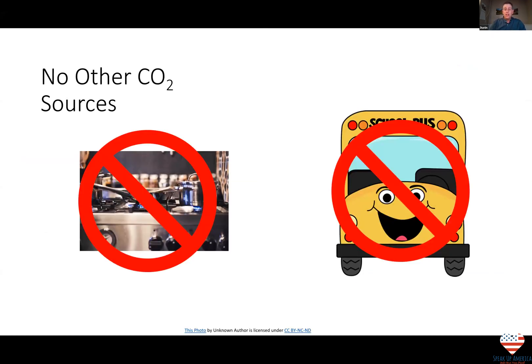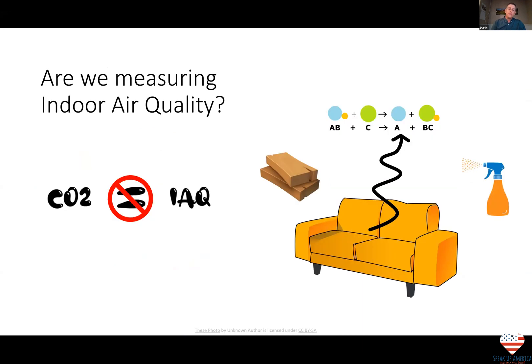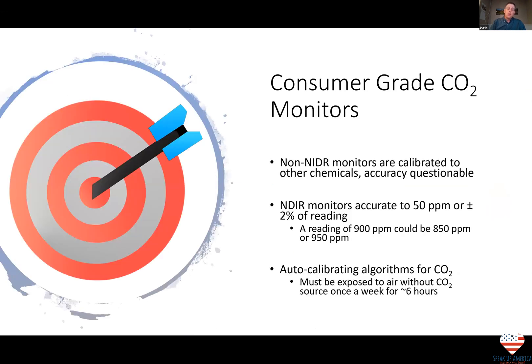If we want to use CO2 as a ventilation indicator, we need to make sure there are no non-human sources that would impact concentration, such as indoor combustion or vehicles idling outside near indoor air intakes. It's also important to note that CO2 is only a proxy for human emissions and does not account for many other things that impact indoor air quality. Consumer-grade CO2 monitors have limitations. Non-NDIR sensors can have errors depending on their calibration. Although NDIR sensors report values to three significant digits, they're only accurate to about 50 ppm. All sensors can drift over time, so it's important to measure the difference between indoor and outdoor CO2 concentrations, as that gives the most accurate and reliable data.